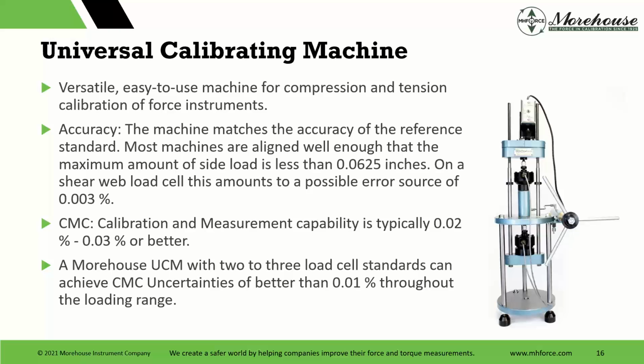If you want to get better than the 0.02 to 0.03 I have listed here, it's going to take some technician training, some really good reference standards, and good repeatability when you do your repeatability studies. It's very obtainable with time and practice. But most labs are edging closer to 0.03, and the other reason is they're not making multiple standard changes. The better you want your uncertainty to be, going back to Euromet Guide CG4, ISO 376, and some of the others, the more standard changes might be required. To maintain something like 0.01, you might need 3 or 4 load cell standards, for 0.02, that might be 2 to 3. If you want to maintain 0.03, 0.04, you might get away with just 1 standard.